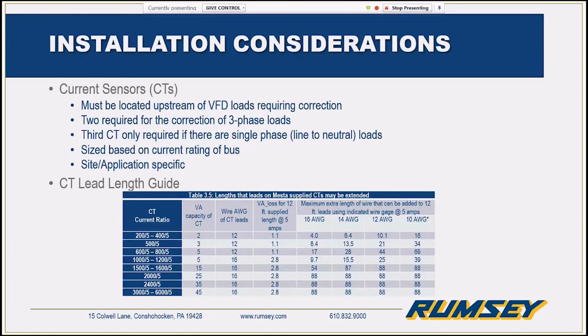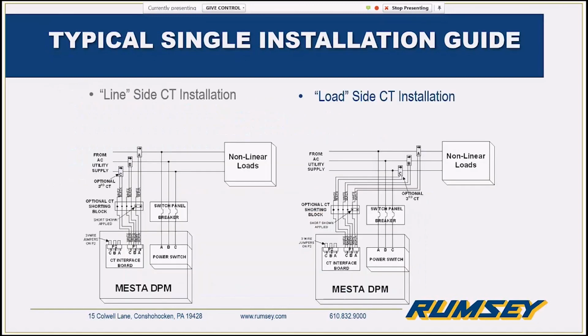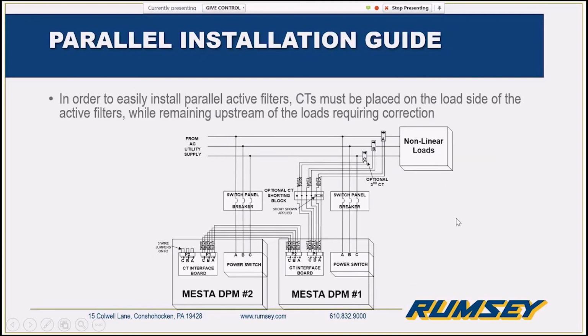This isn't too important, but just a reminder, you need those two CTs for the correction of 3-phase loads. We have line and load side CT installation. When you're looking at one filter, it doesn't really matter. All that means is you have the CTs upstream of the feeder breaker or downstream of the feeder breaker. The only time it really comes into play is if you have parallel installed active filters. So if you're able to put the CTs on the load side, you can share one set of CTs between all of our active filters down the line.